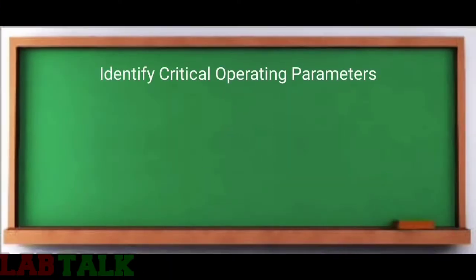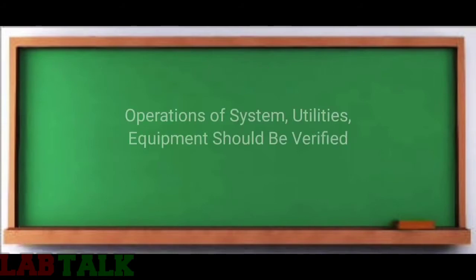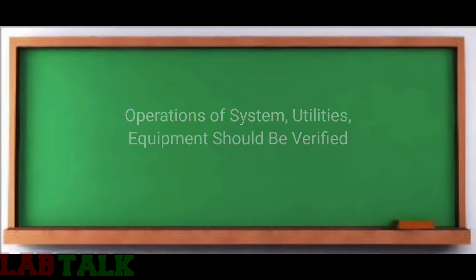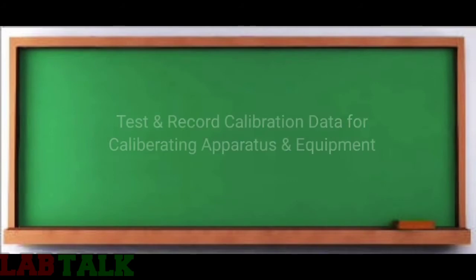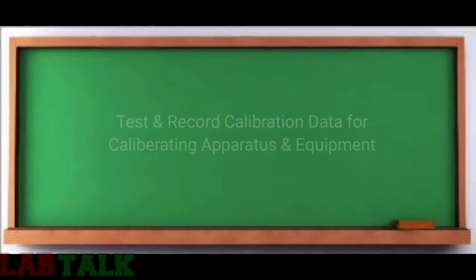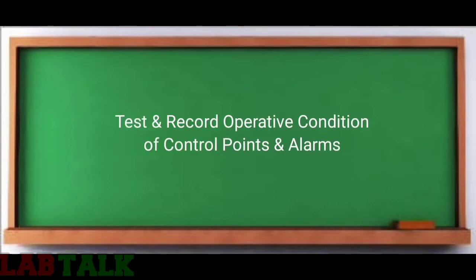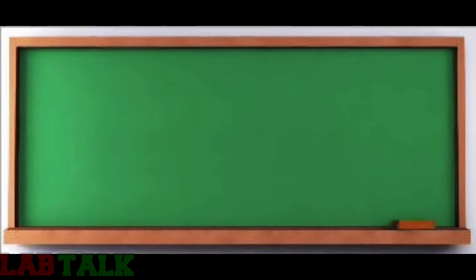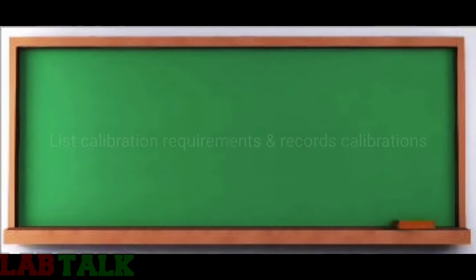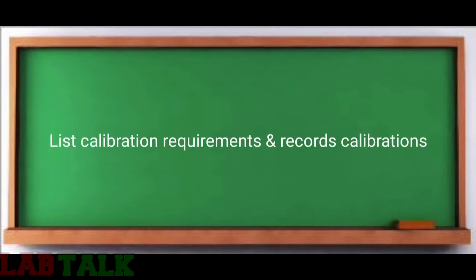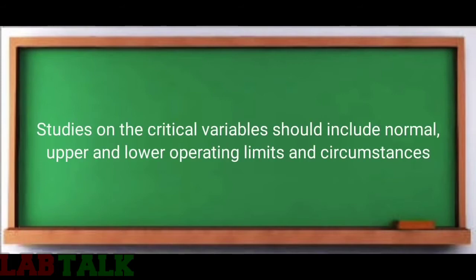Coming to the step-by-step procedure: critical operating parameters should be identified for the equipment. Systems, utilities, and equipment should operate correctly, and their operations should be verified in accordance with the OQ protocol. Test and record calibration data for calibrating apparatus and instruments. Test and record operative conditions of control points and alarms, test and record outputs, list calibration requirements for the system under test, and maintain records of calibration.